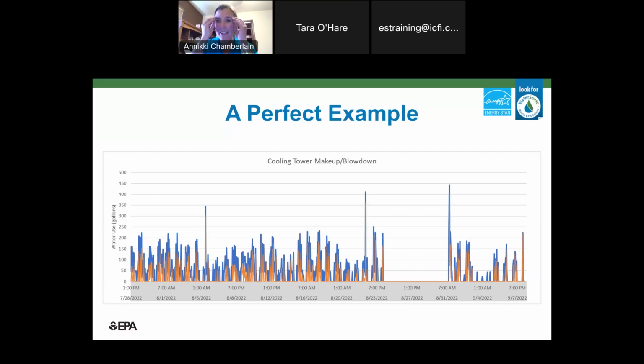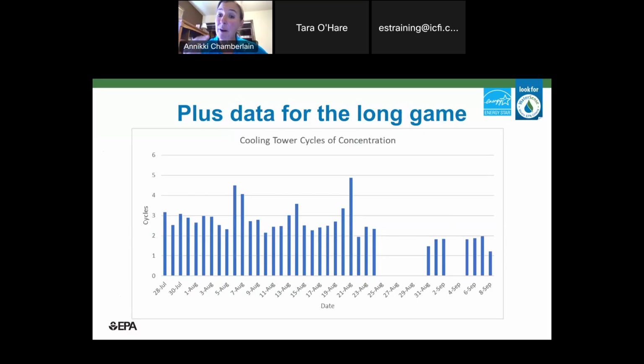After they saw this, with high resolution cellular monitoring he would have, as normal procedure, opened up the dashboard, seen that my tower hasn't blown down or made up, and gone to the site. After we saw this, they said let's do this everywhere. So we're doing it on their cooling towers and their boilers. Very exciting. Plus, that water volume gives them the ability to see their cycles of concentration. So not only is it day-to-day operations protecting the machine, but I can see what my efficiency is.